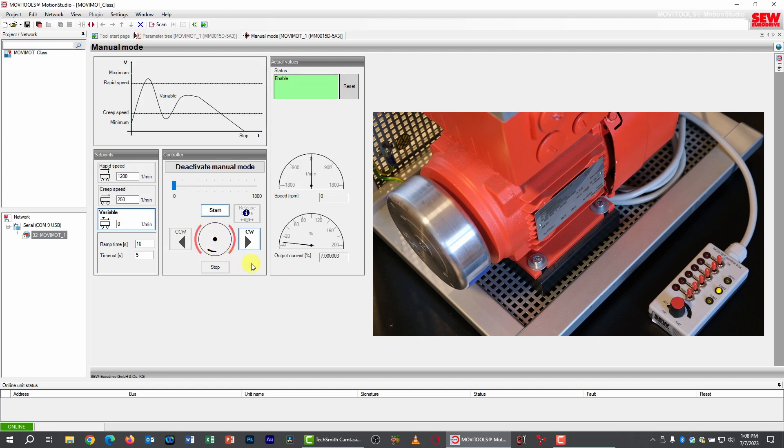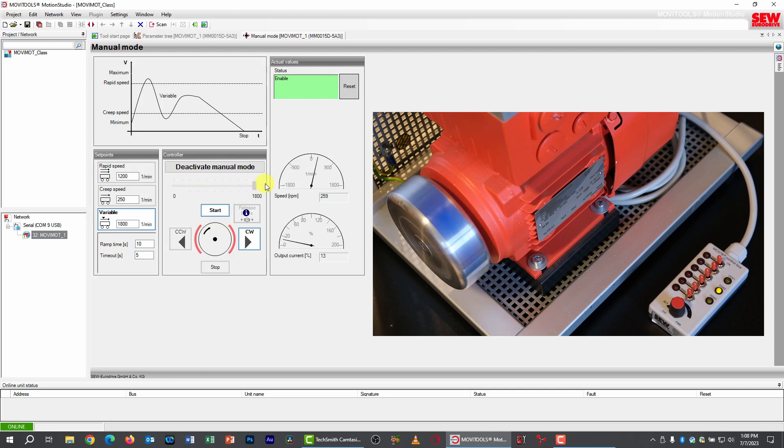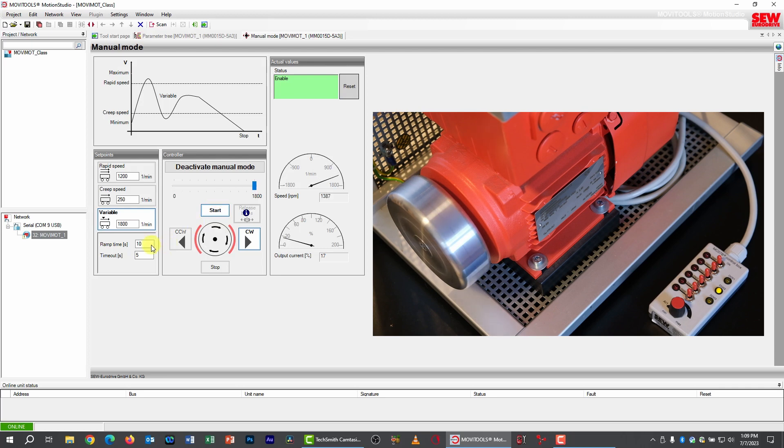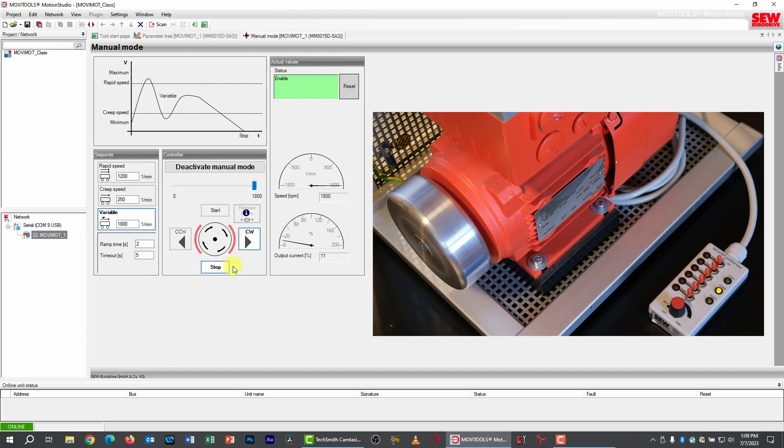But the motor isn't actually turning because now it's allowed to come to a full stop. But if I adjust my slider, of course, then it's going to accelerate up to that new maximum of 1800 RPM. And it's doing it rather slowly because my ramp time has reverted back to 10 seconds. Let's change that back to 2 so we don't have to wait forever to make speed changes. And if we do a stop now, of course, we'll come to a stop pretty quickly.